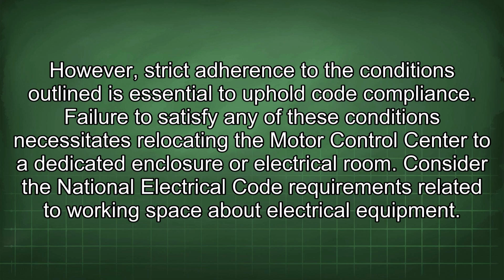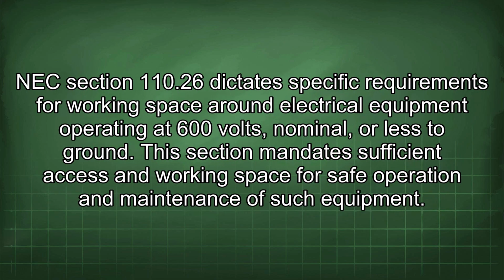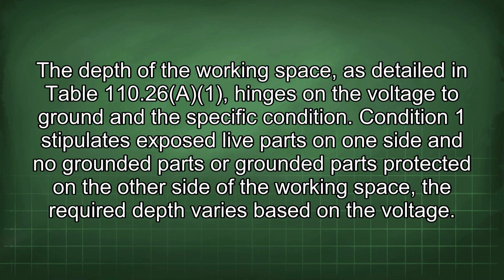Consider the National Electrical Code requirements related to working space about electrical equipment. NEC Section 110.26 dictates specific requirements for working space around electrical equipment operating at 600 volts, nominal, or less to ground. This section mandates sufficient access and working space for safe operation and maintenance of such equipment. The depth of the working space, as detailed in Table 110.26(A), hinges on the voltage to ground and the specific condition. Condition 1 stipulates exposed live parts on one side and no grounded parts or grounded parts protected on the other side of the working space. The required depth varies based on the voltage.